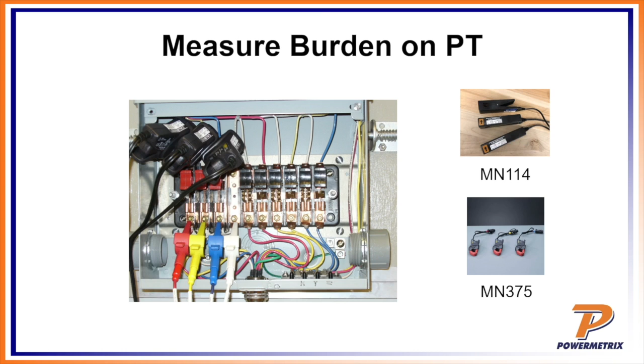That added feature of the burden measurement you can do with the 3 series applies to both PTs and CTs. We don't talk about it enough on the PTs, but that's only because people don't test PTs as much here in the U.S. It's a definite feature, since burden affects PTs just like it affects CTs, but we don't talk about it much since not that many people test it. You'd use those small probes to pull that off as well.